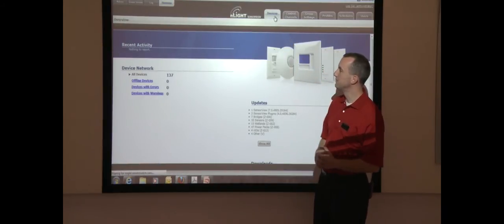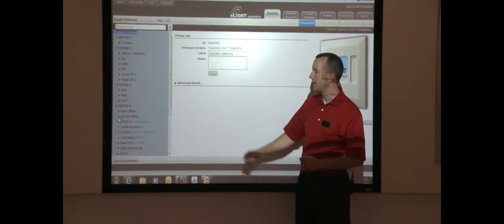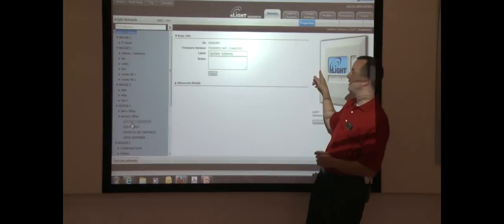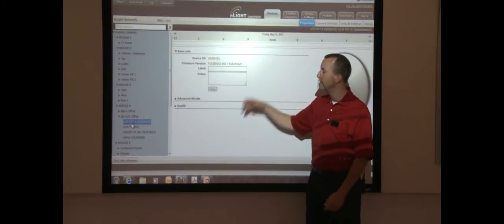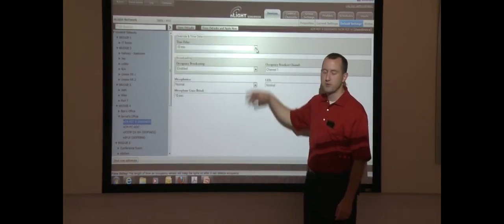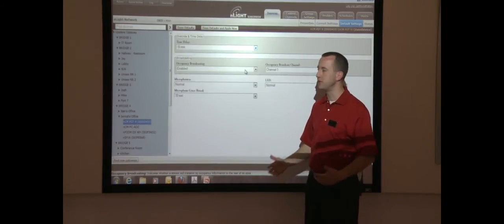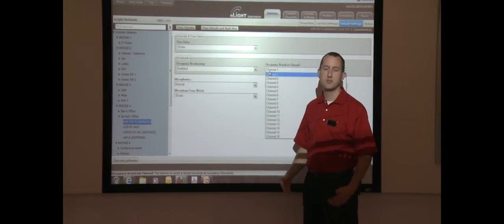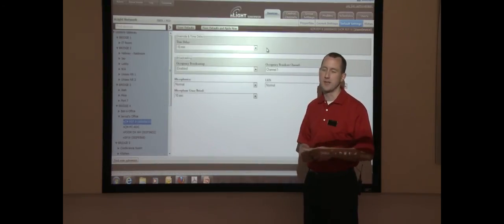If you go to Devices, you actually see a whole tree of the entire building. We're going to go into one particular office, which is Jared's office here. You'll see all the devices are shown over here with the image as well as basic info. We can drill into all the devices. Here we have an occupancy sensor. You can name it. If we go into Settings, you'll see all the settings and parameters of every device, such as time delay, can be set remotely. You can set up what devices are tracking each other. Special modes of sequence of operation all can be done through this remotely. You can do them one device at a time, one zone at a time, or you can group them together and set many devices all at the same with one click.